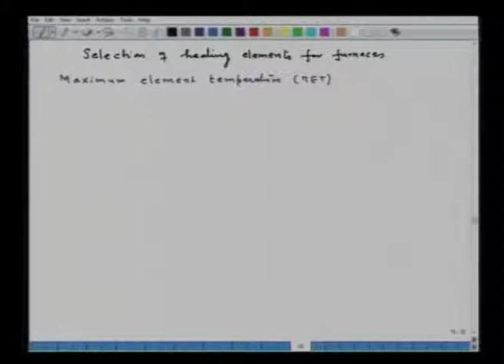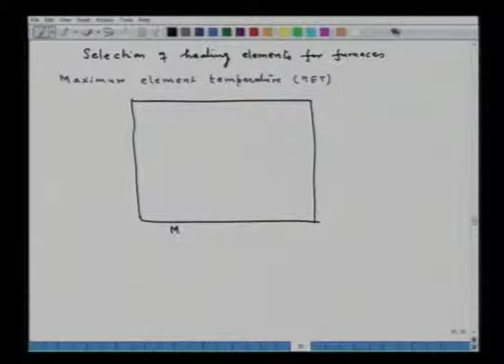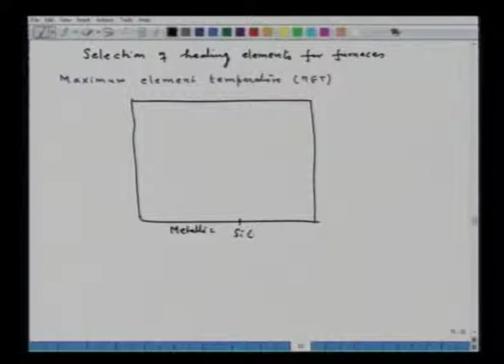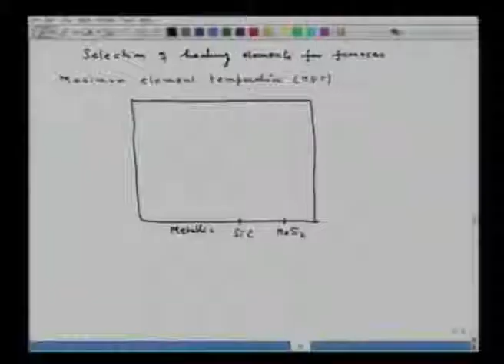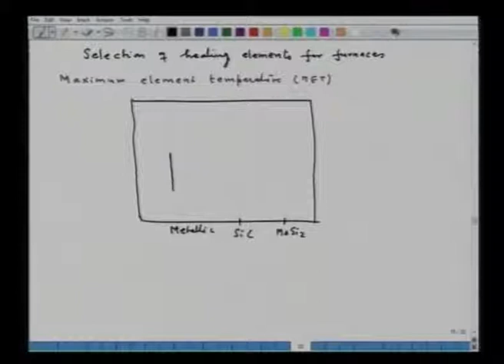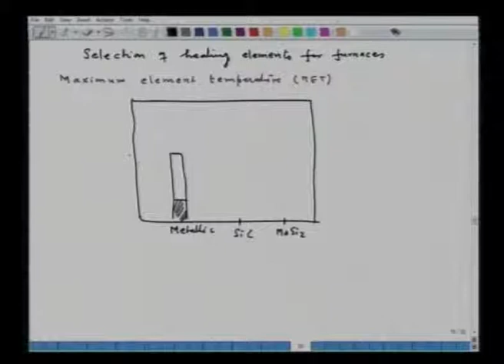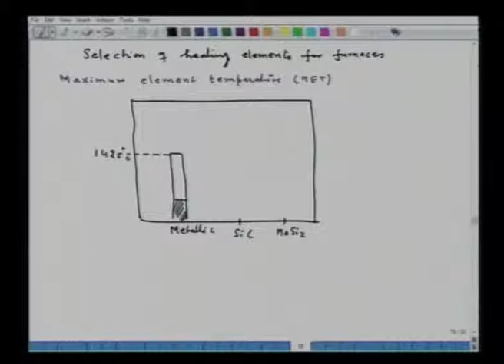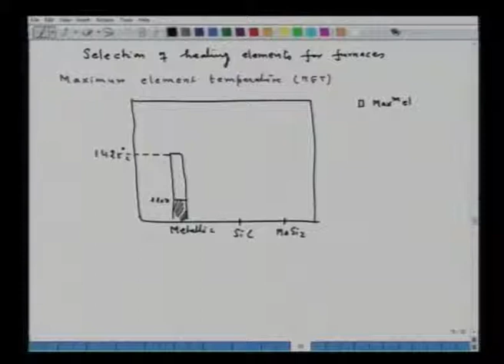Now, for that I am selecting three different types of heating element that I am putting over here. Here I take metallic heating element, this is metallic, this is silicon carbide and this is MoSi2. So, I am comparing these three heating elements for selection purposes. The metallic elements can be used up to around 1425 degrees Celsius and this temperature is around 1100 degrees Celsius. So, this represents the maximum element temperature, and this is the useful limit.